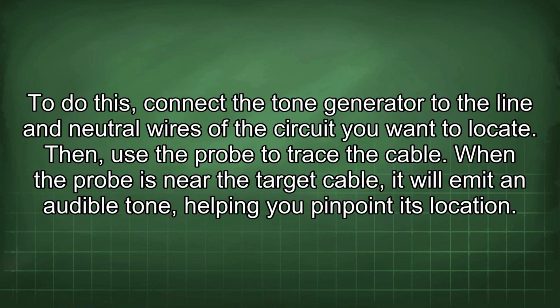To do this, connect the tone generator to the line and neutral wires of the circuit you want to locate. Then use the probe to trace the cable. When the probe is near the target cable, it will emit an audible tone, helping you pinpoint its location.